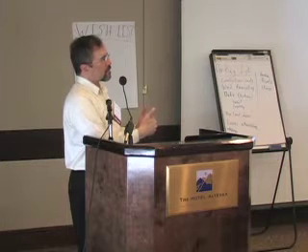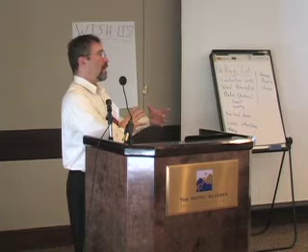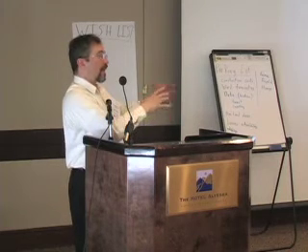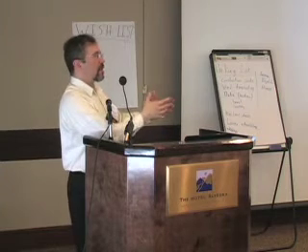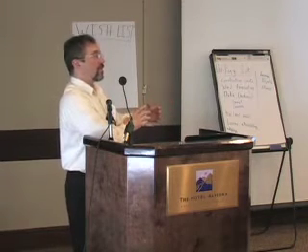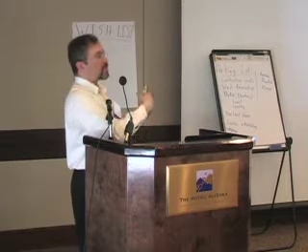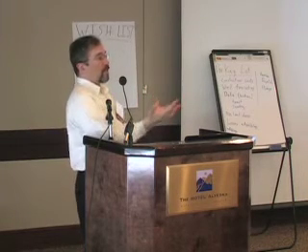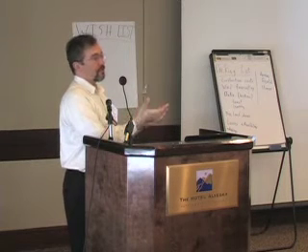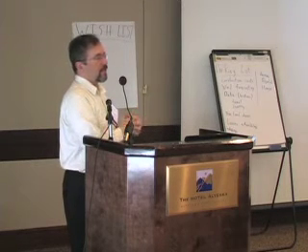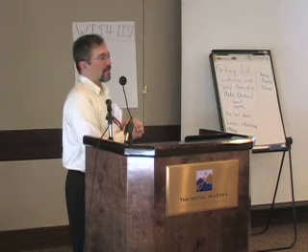All of the equipment that we installed today is now a sunk cost, with no capital cost. It still has a replacement cost, still has fuel and O&M costs, but the capital cost is zero. We treat that as existing, and then ask HOMER, well, we have a bigger load now, what additional equipment is needed? It's not quite as automated.